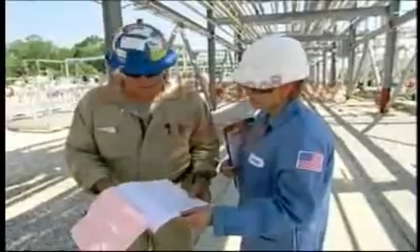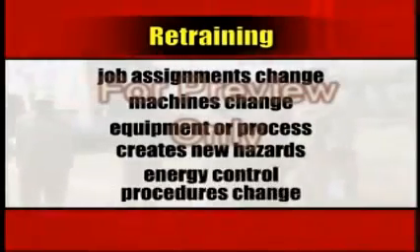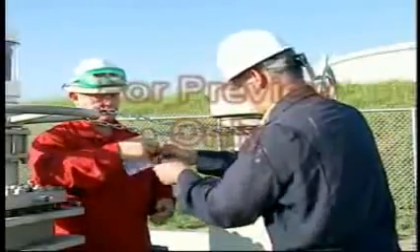It is important that all employees follow the central rule: no one should ever try to start equipment that is locked out or tagged out. Employees should be retrained when their job assignments change, the machines change, equipment or process creates new hazards, and when energy control procedures change. An employee is also required to be retrained if during an inspection he or she doesn't appear to follow or fully understand the procedure.